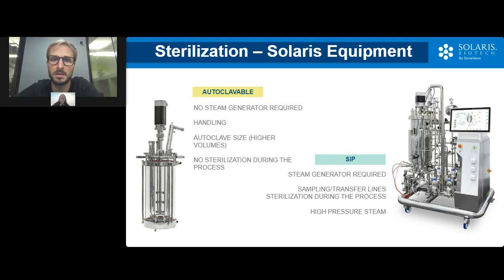In addition, no sterilization can be done during the process on any peripheral line, which are usually silicone tubes managed through peristaltic pumps. Solaris equipment has been designed to grant optimal handling and fast setup prior to autoclaving. Getting higher with the volumes, autoclaving is not an option anymore. Sterilizable in-place solutions require steam availability, but give the chance to sterilize the bioreactor and its components in loco. The peripheral lines can be sterilized during the process to lower the chances of contamination due to additions, sampling, and transferring from or to other plant equipment. Along with the main bioreactor, all the feeding tanks, harvest tanks, and other ancillary equipment must be autoclavable or sterilizable in place, which is something that Solaris can also offer.